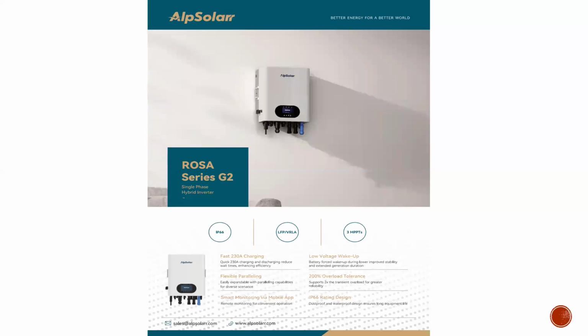So it has 3 MPPT. This guy has 3 MPPT, and I think I should just discuss the MPPT once and for all. So it has 3 MPPT and 4 strings. The MPPT1 has 2 strings under it, and those 2 strings are internally parallel. And then the MPPT2 and MPPT3 have just 1 string each. So MPPT1, having 2 strings, has the highest PV input power. It can take 8,400. That is the PV input power of the MPPT1. And then the MPPT2 and MPPT3 can take 4,800 each.